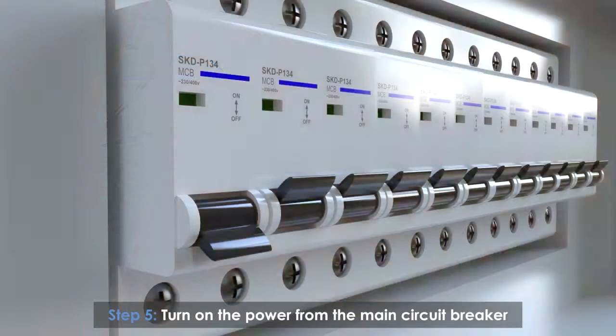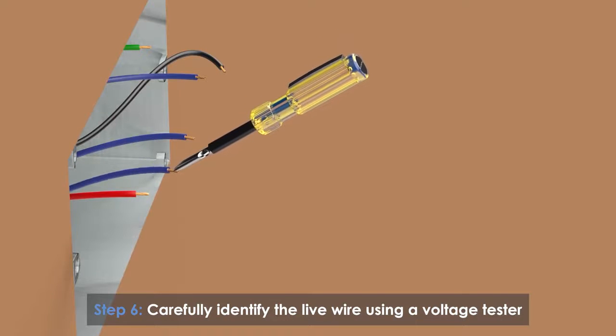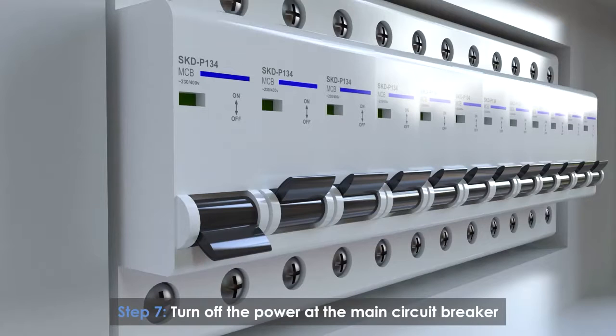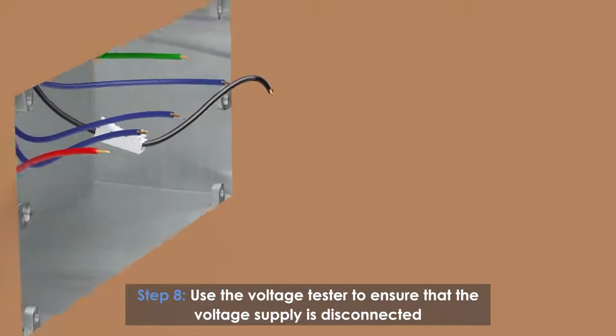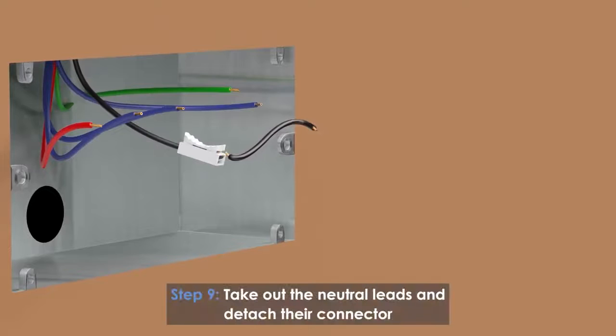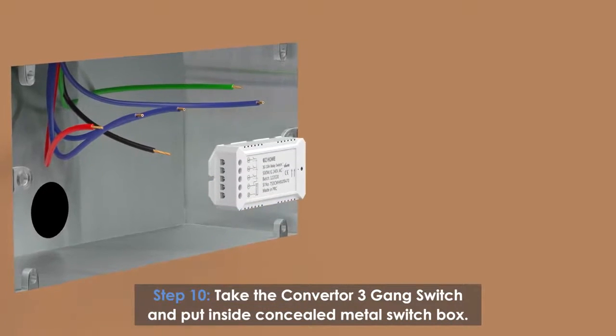Turn on the power at the main circuit breaker and carefully identify the live wire using a voltage tester. Turn off the power again at the main circuit breaker and use the voltage tester to ensure the voltage supply is disconnected. Take out the neutral leads and detach their connector.